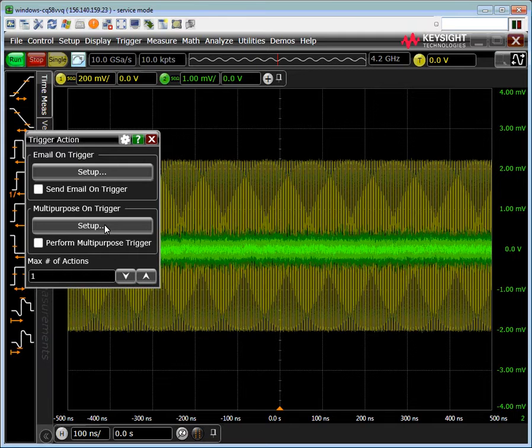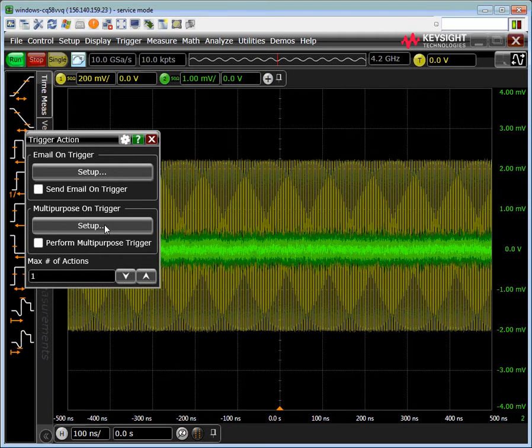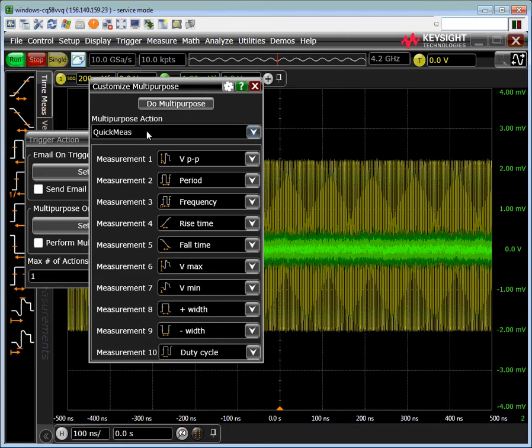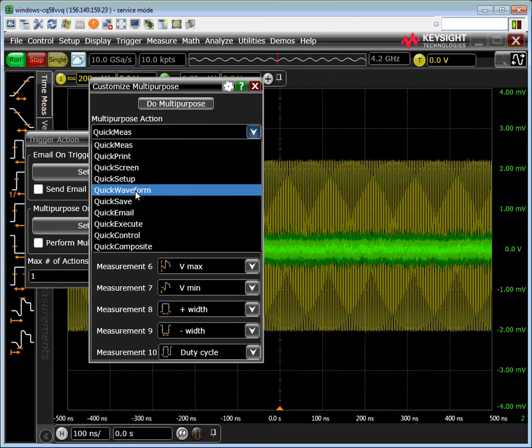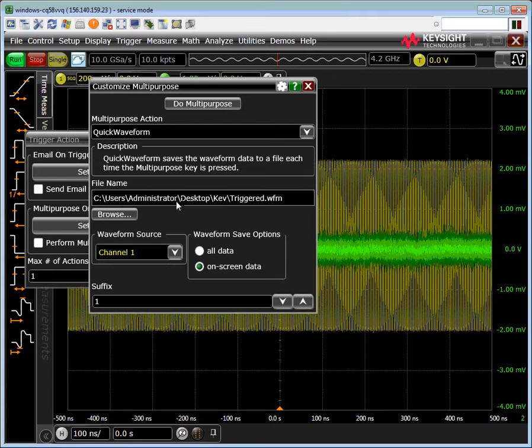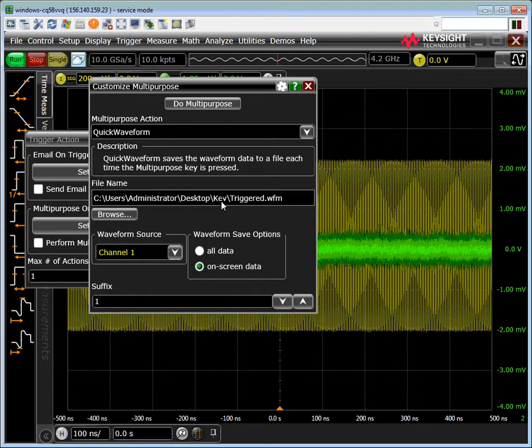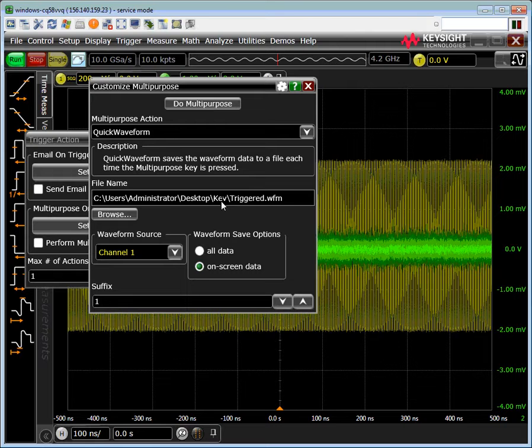For our purposes we're going to come over here and go to setup. We're going to change the multi-purpose action to quick waveform. This will allow us to save a waveform each time a trigger event occurs.